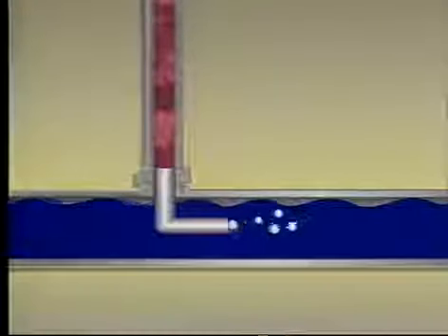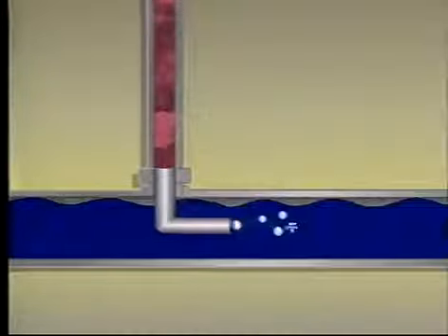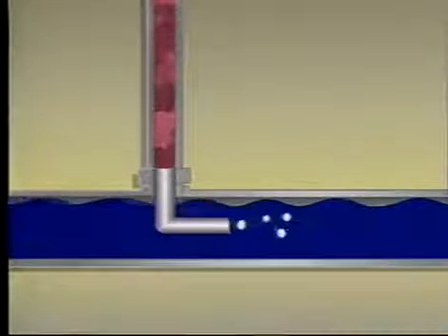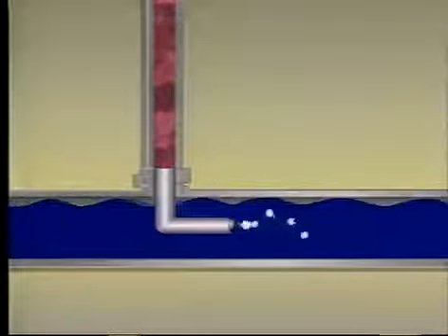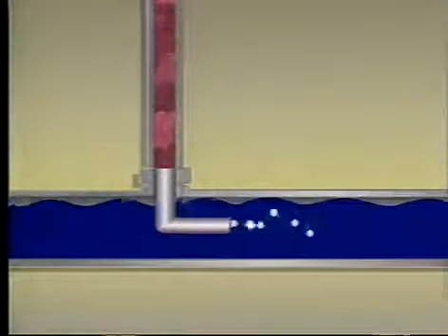To minimize such a disturbance, the drip trap should discharge in the direction of condensate flow by means of a special fitting. This method of controlling thermal shock, called sparging, reduces the concentration of collapsing steam bubbles and keeps the action from occurring by the pipe wall.